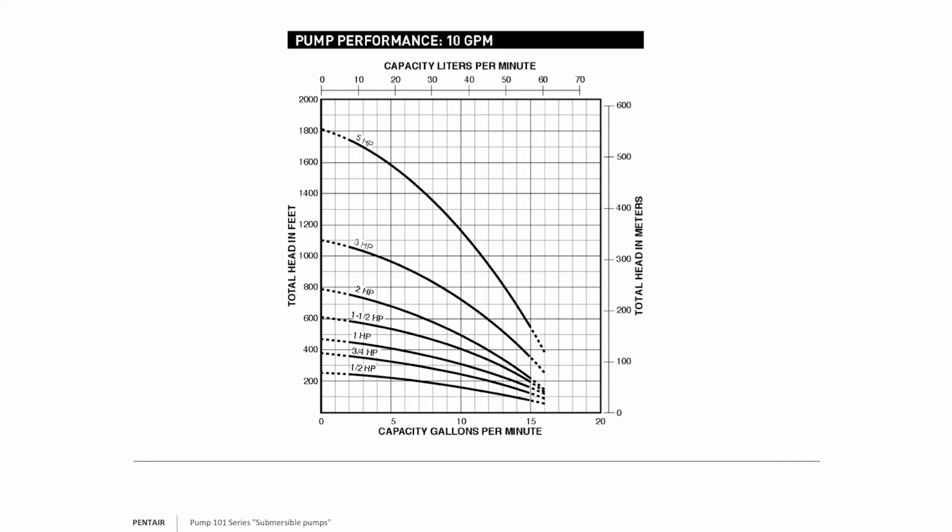Now, also you see on this curve, you'll see dashed lines. On the left side, we want you to stay away from that because that's your minimum constant sustainable flow. If you're using a variable frequency drive, you definitely don't want to be over there because you're going to have upthrust issues and other cavitation issues. As you go to the far right of the curve, if you've been to any of my other lectures, you'll know that I've explained this.